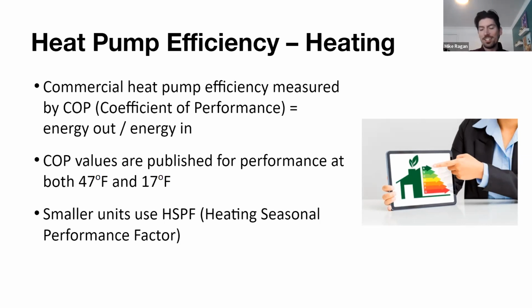Next slide, I'm going to get into the advantages of heat pumps, but with heat pump technology, you're actually able to get a COP of greater than 1. I'll discuss that in a minute. Alex touched on that a little bit later. The fact is that we're not generating heat, we're transferring heat. If we're able to move heat from one location to another, we're not generating that heat. We're not burning gas, we're not burning oil in order to get heat. We're taking it from somewhere and moving it elsewhere. It's a much more efficient way of getting heating BTUs.